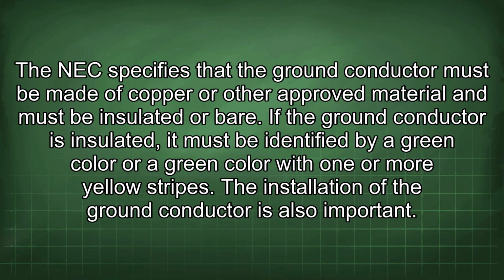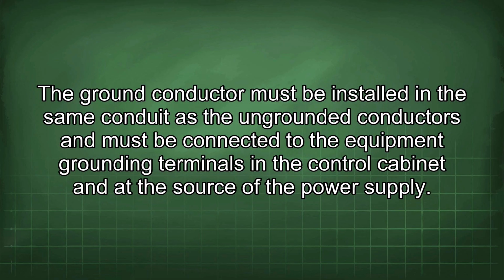The NEC specifies that the ground conductor must be made of copper or other approved material and must be insulated or bare. If the ground conductor is insulated, it must be identified by a green color or a green color with one or more yellow stripes. The installation of the ground conductor is also important. The ground conductor must be installed in the same conduit as the ungrounded conductors and must be connected to the equipment grounding terminals in the control cabinet and at the source of the power supply.